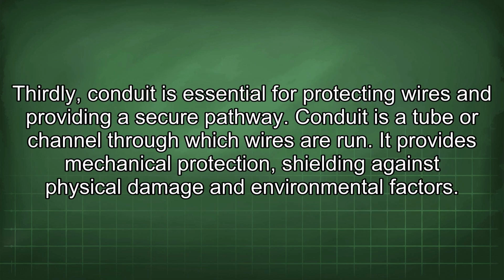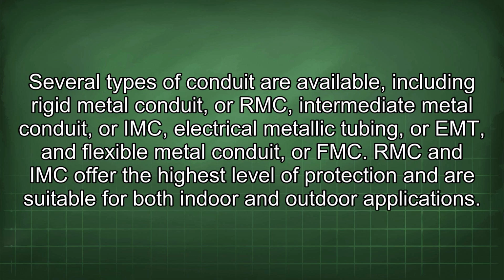Thirdly, conduit is essential for protecting wires and providing a secure pathway. Conduit is a tube or channel through which wires are run. It provides mechanical protection, shielding against physical damage and environmental factors. Several types of conduit are available, including rigid metal conduit, or RMC, intermediate metal conduit, or IMC, electrical metallic tubing, or EMT, and flexible metal conduit, or FMC. RMC and IMC offer the highest level of protection and are suitable for both indoor and outdoor applications.